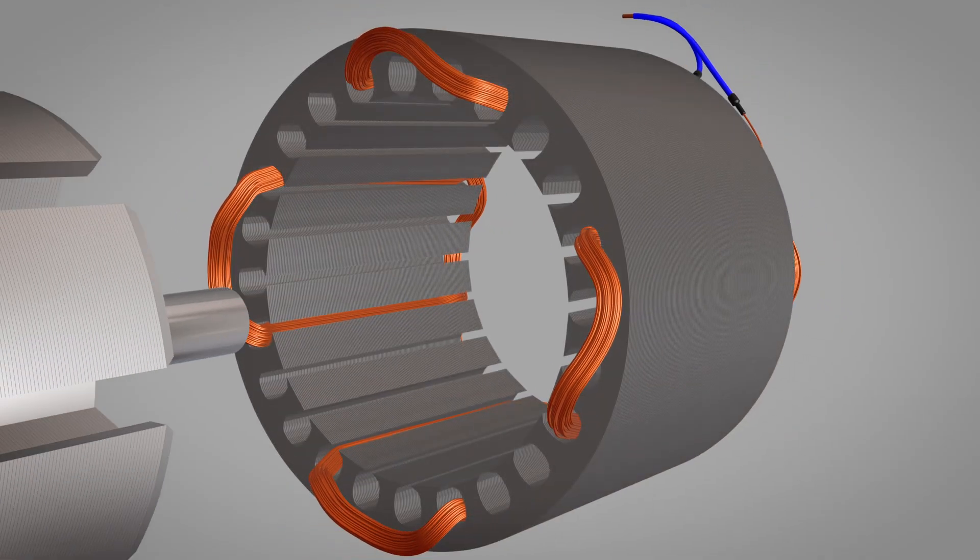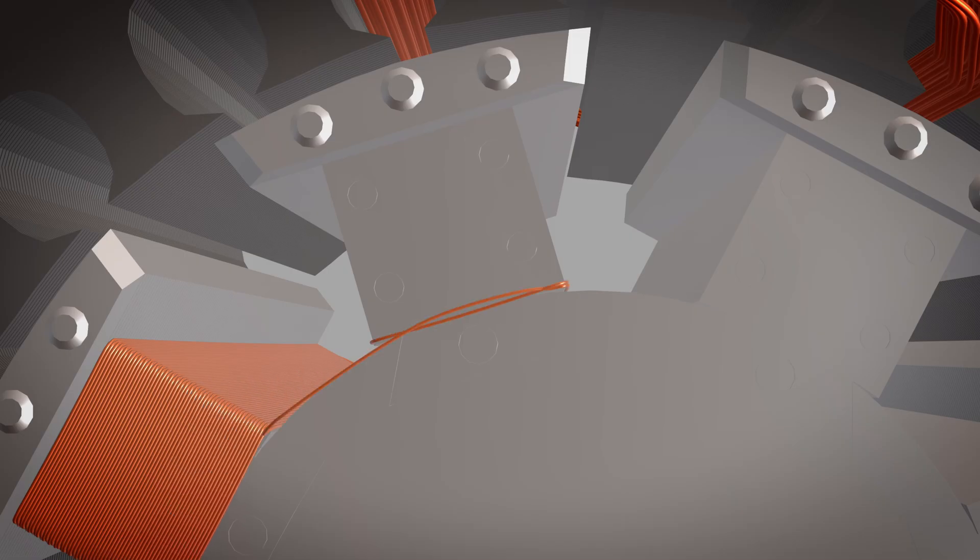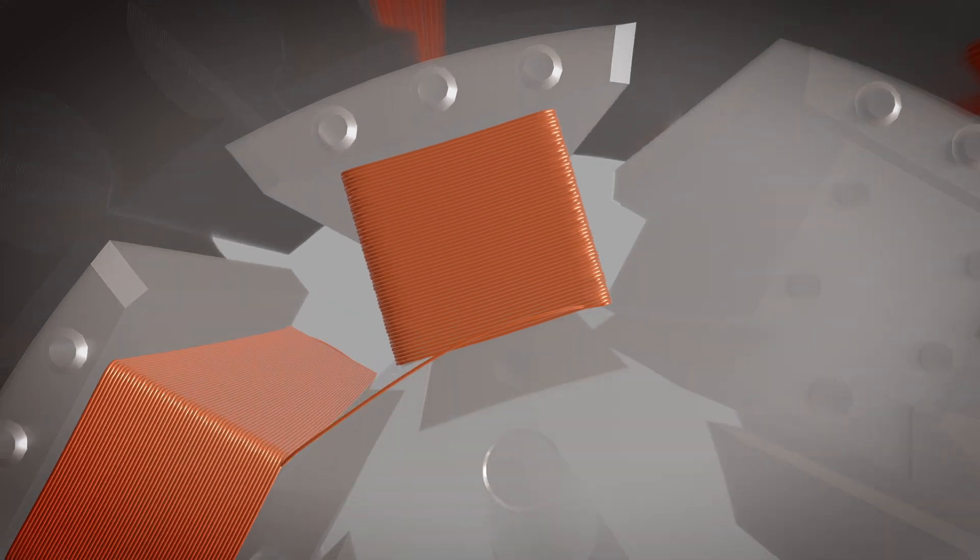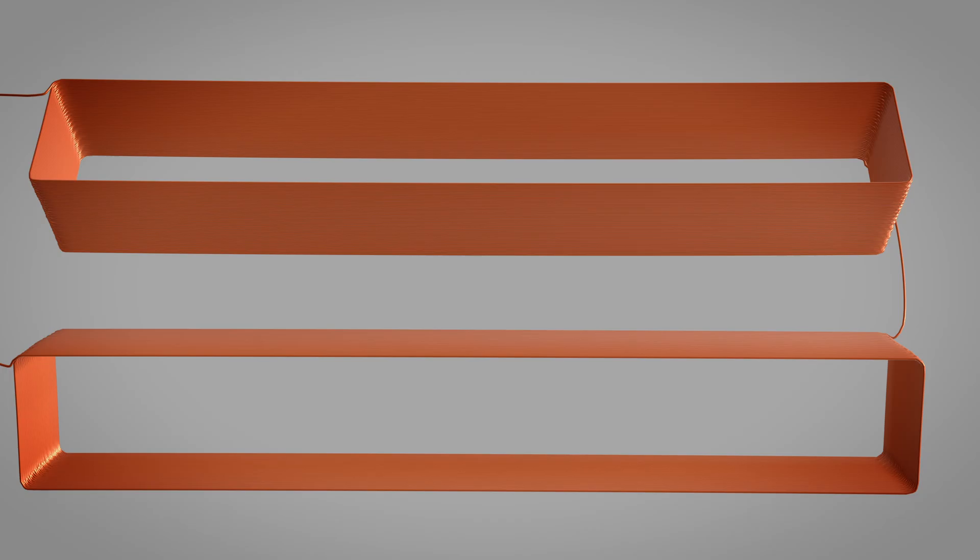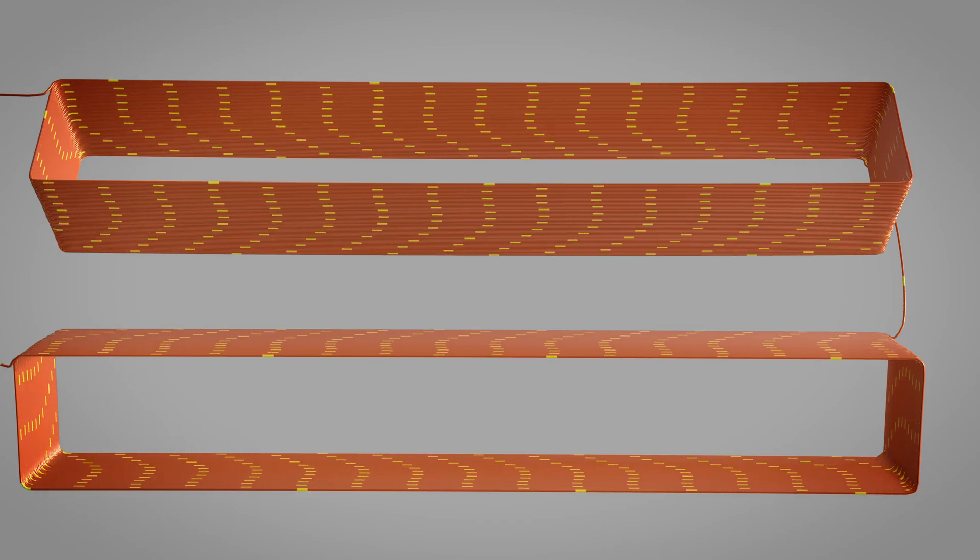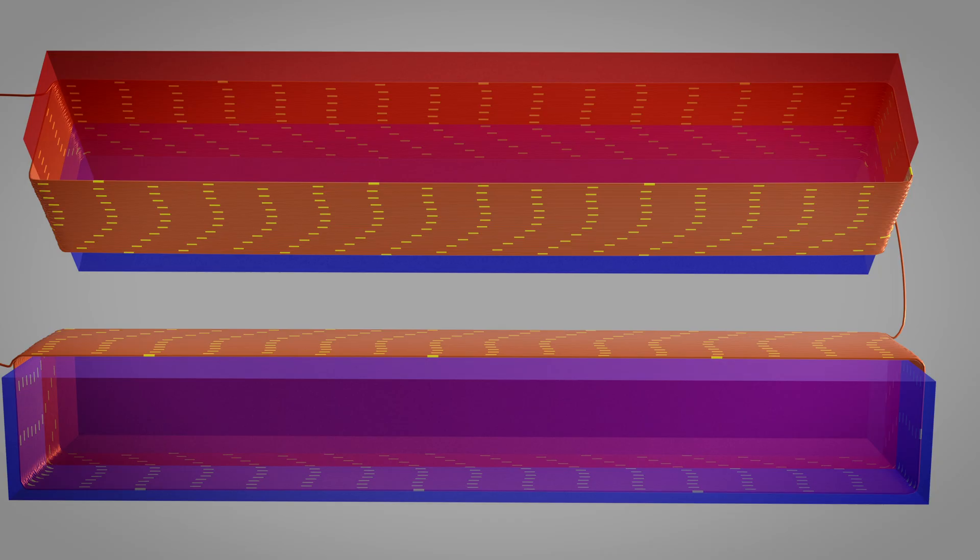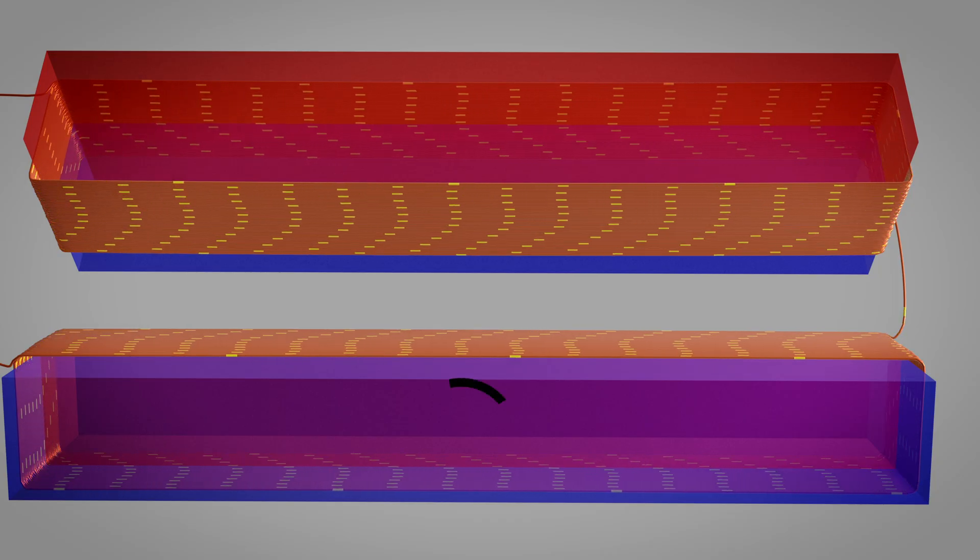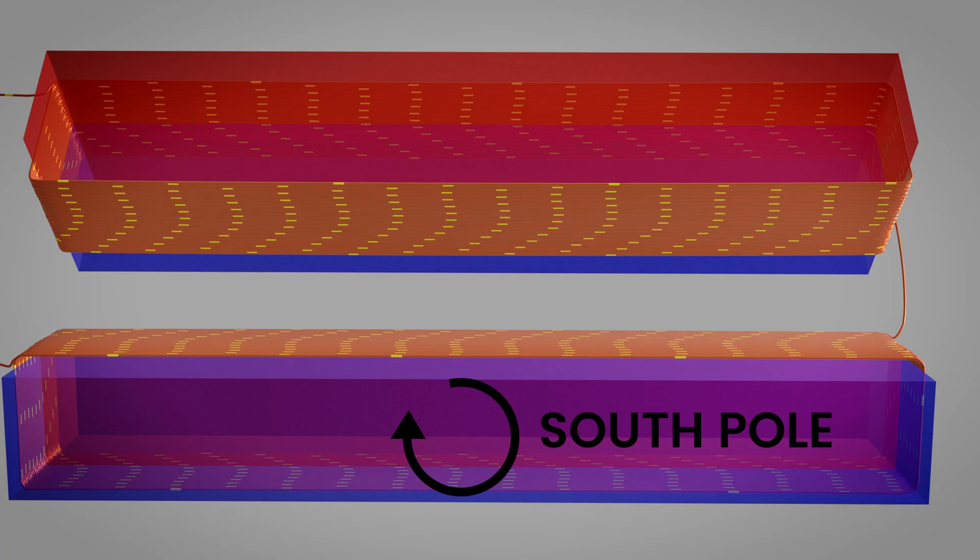Now let's introduce the rotor. We'll start with two adjacent salient poles, projecting electromagnets that form the foundation of our magnetic field generation. Each pole has a concentrated field winding wrapped around it connected in series. When we send DC current through these windings, they become powerful electromagnets. Here's where the clock rule becomes crucial. If current flows clockwise around the first pole when viewed from the end, it creates a south pole.